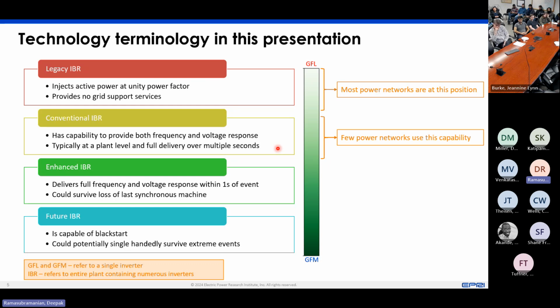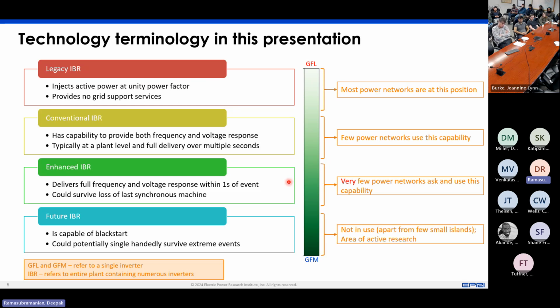You do require a lot of voltage control right now at the plant level in most of the newer inverter-based resource plants connected to the grid. So there are a few networks that use this capability in the field that we know of. There are even fewer networks that utilize this enhanced capability, essentially delivering full frequency and voltage response within one second of an event. And there are only a few island systems that are looking at this future inverter.